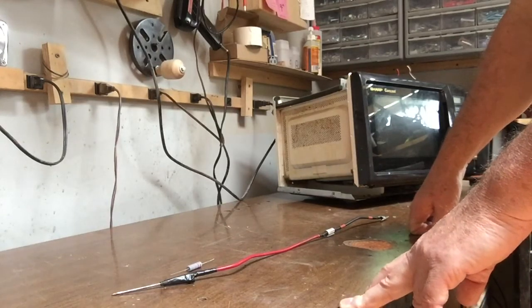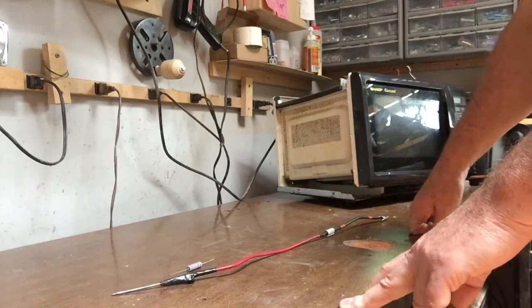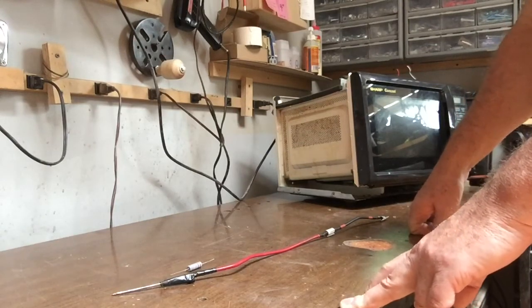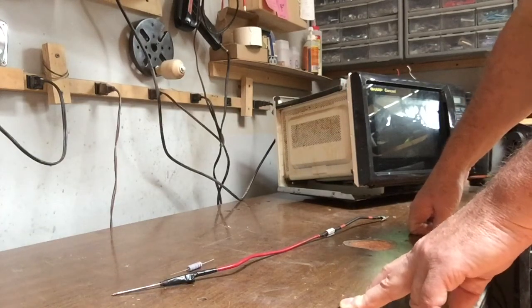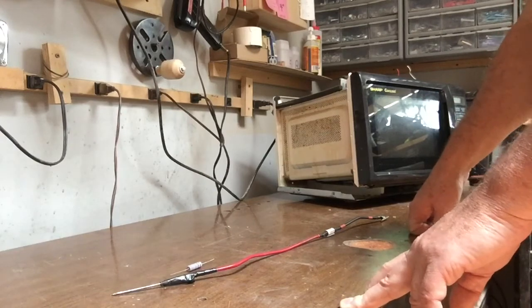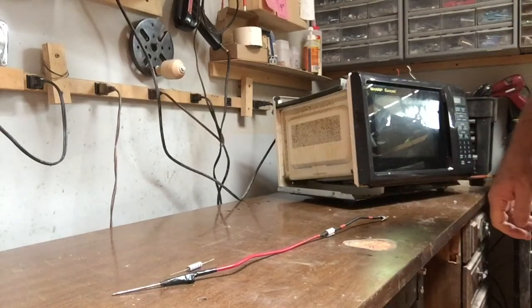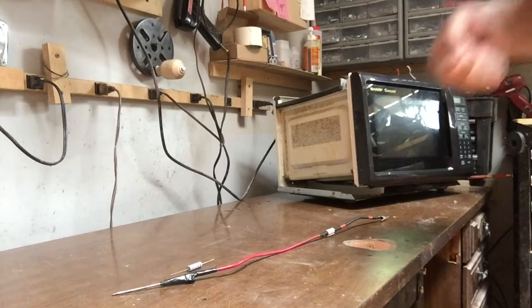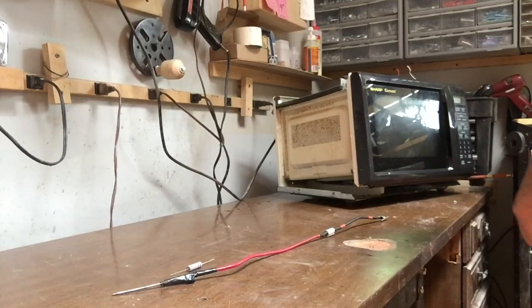So you're going to need to discharge the capacitor before you do anything in there. Although it's unplugged and shut off, it still may, and probably does, carry serious voltage. The old timers used to take a screwdriver and put it across both terminals on the capacitor, which would cause a big pop and a big spark. That's very dangerous. If you're working in a commercial or industrial building and you don't have a hot works permit, you can't go around shorting things out, creating sparks.